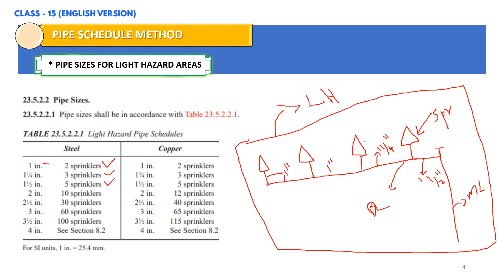Here we have only four sprinklers, and for the fifth sprinkler position we can go ahead with 40 mm — one and a half inch. From 6 to 10 sprinklers, we need to use two-inch pipe. From 11 to 30 sprinklers, we need to go ahead with two and a half inch pipe. From 31 to 60 sprinklers, we can use three-inch pipe. And for 61 to 100 sprinklers, we can consider three and a half inch or four-inch pipe.